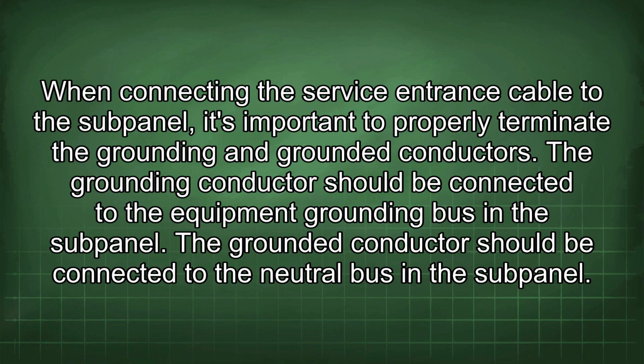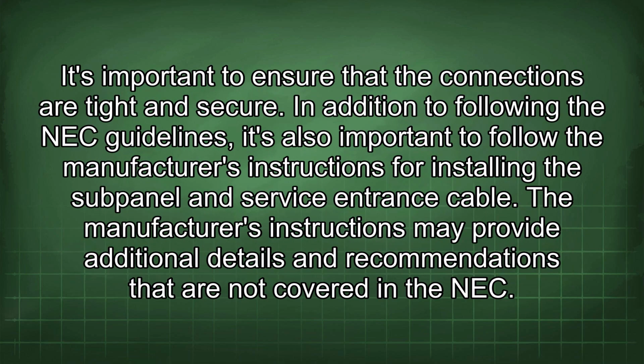When connecting the service entrance cable to the subpanel, it's important to properly terminate the grounding and grounded conductors. The grounding conductor should be connected to the equipment grounding bus in the subpanel. The grounded conductor should be connected to the neutral bus in the subpanel. It's important to ensure that the connections are tight and secure.